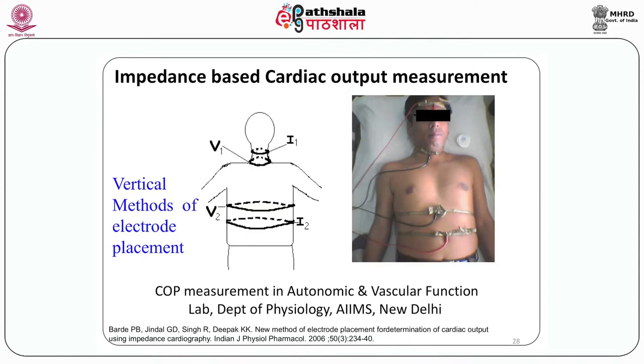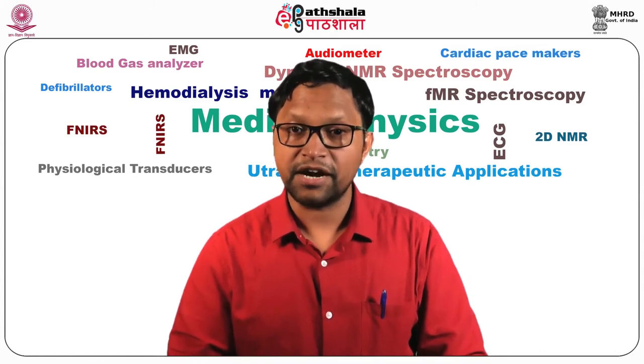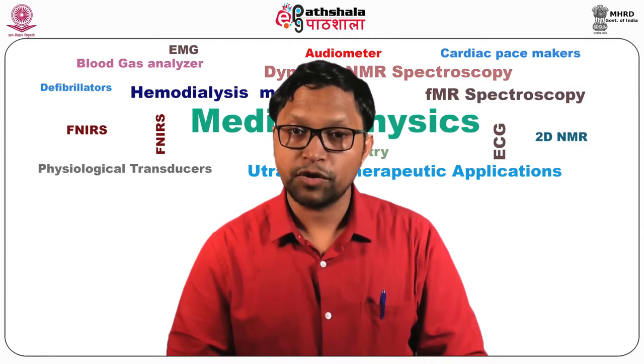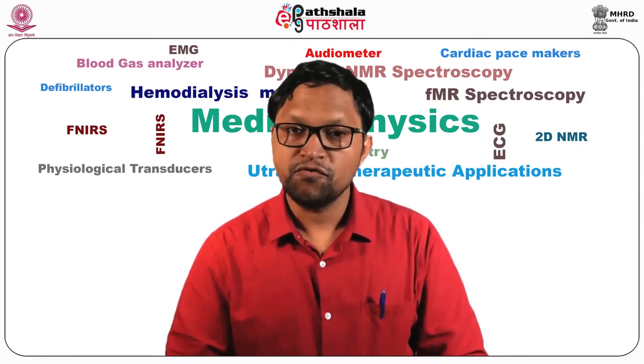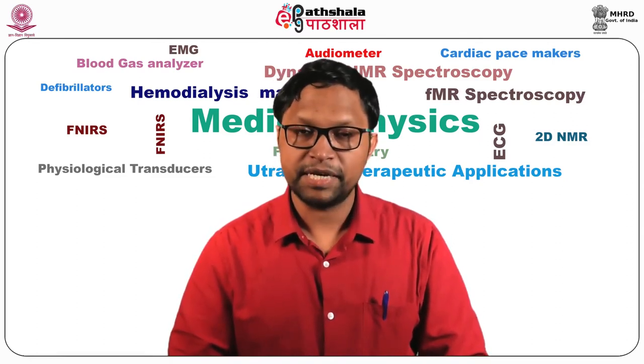Since impedance plethysmography measures the volume flow to the area, when the electrodes are placed across the chest, the measurements provide the value of cardiac output. This is called impedance cardiography. This has been validated with standard techniques like thermodilution and Fick method. The middle trace shows the typical record of thoracic impedance waveform from which cardiac output can be calculated by using well-established equations.